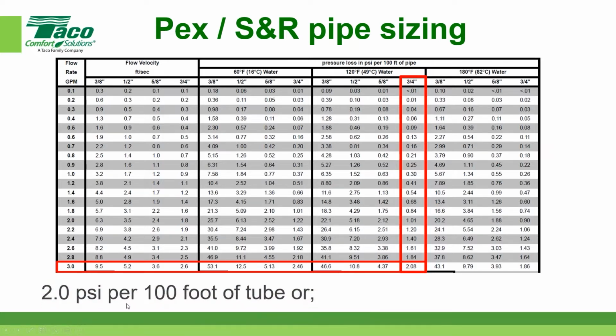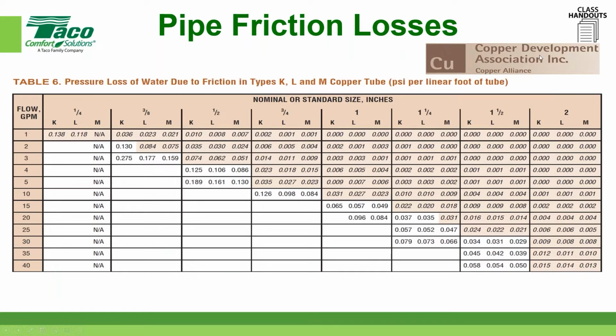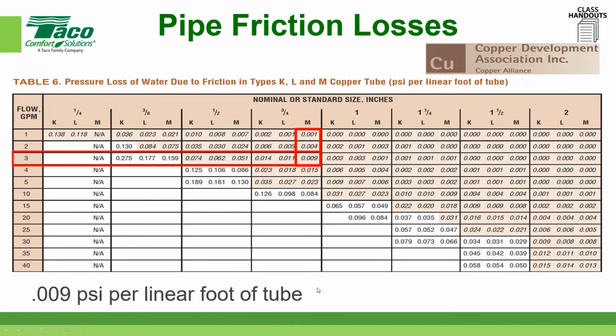Okay. So 2 psi per 100 foot of tube, or I like to do it this way, 0.02 psi per linear foot. That keeps you from fractionalizing the 100-foot number. So I just take everything back to per foot, and then I times it by the total number of feet. It's just the way I like to do it. You could do it either way. As I'm going to show you now, here's from the Copper Development Association. Here's 3 gallons a minute through a piece of 3/4 type M, and that tells me what the pressure drop is in psi per linear foot of tube. Okay, per linear foot is my multiplier, or 0.9 per 100 foot. So that way you just pick and choose which way you like to do it. Many people like the 100-foot increment. I prefer the per foot because it's easier for my brain to not have to fractionalize things.